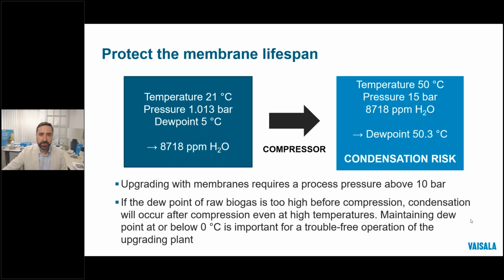So measuring the dew point before compression can help protect against this type of failure and could negate the need for a separate drying membrane in the system, maybe. Of course, this all goes back to the control of the dehydration system, which is where most of this can be managed. Next, please.